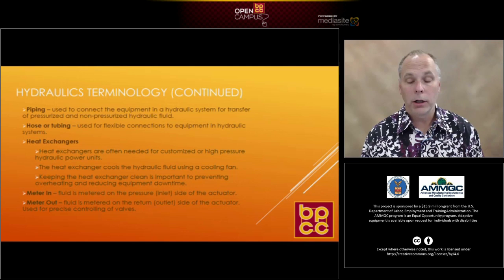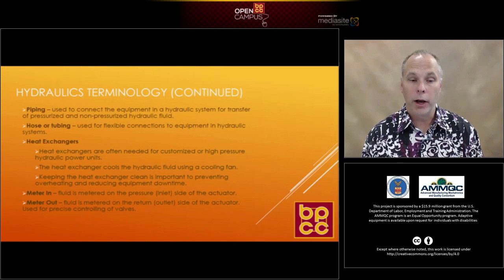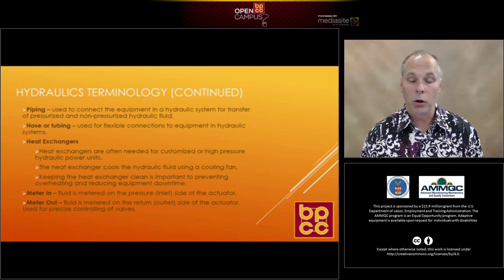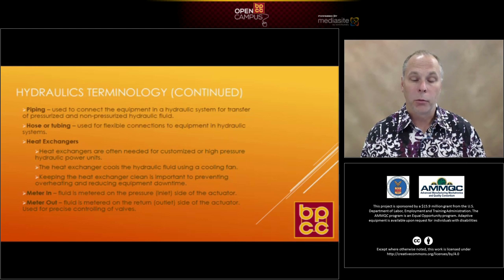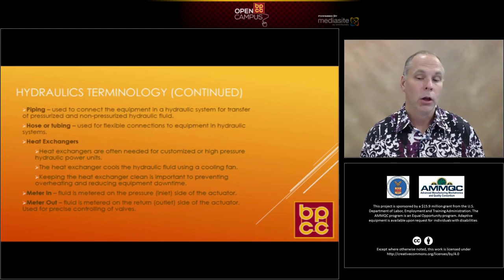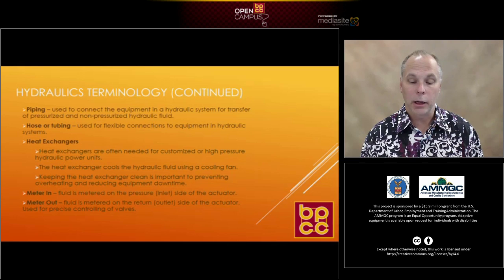Regarding flow and controlling your actuator: if you want your hydraulic cylinder to move at a certain speed, you'll have flow control valves on the inside and outside of that actuator. The best way to achieve precise control of your actuators is to use the metered outside approach — utilize your flow control valve on the outside, adjust it, and that will keep more precise control of your actuators.